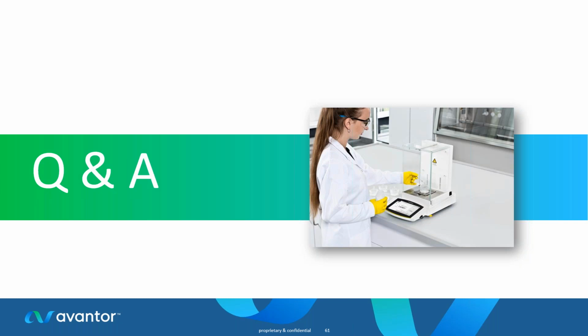So if you know that you have a problem with static electricity or charge, either on your tare vessel or on your sample or on both, then using an anti-static tare vessel can help the situation. Or of course, if you have an ionizer, as we talked about earlier, an anti-static ionizer, this will fire a corona into the weighing chamber, which will discharge any charge which is residual on either your tare vessel or on your sample.